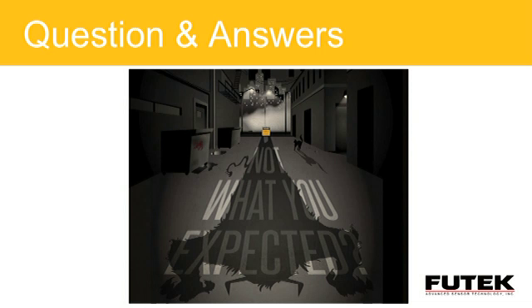Very good question. Absolutely, if the customer has the capability to calibrate it themselves and chooses to perform that task, they can do that. But we've found that because we're set up as ISO 17025, an accredited laboratory, with the tools and equipment right here in-house, it's easier for us to perform that calibration for them. We set it up with the instrument in the engineering units, if it's a display, or we give them the voltage or even millivolt per volt outputs, whatever they choose. We perform that calibration with top grade equipment, provide them a certificate, and it gives them a sense of assurance that they're getting a product that's fully calibrated, so they don't have to worry about doing their own soldering, connections, or calibrations in their own lab, if they even have one.